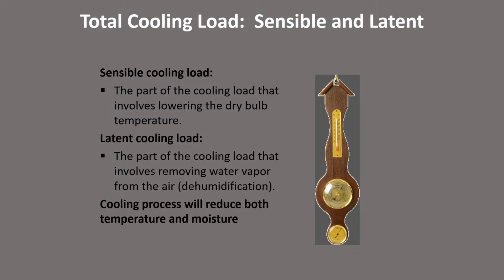Some more definitions. The total cooling load is a combination of both the sensible and latent. Sensible is that part of the cooling load that involves lowering the dry bulb temperature. The dry bulb temperature is just a regular thermometer. The latent cooling load, that's the hidden cooling load, if you will, is the part of the cooling load that involves removing water vapor. The more water vapor you have to remove, the less the sensible capacity is.